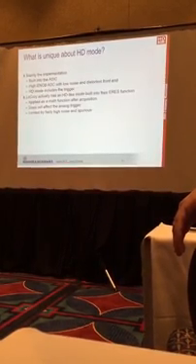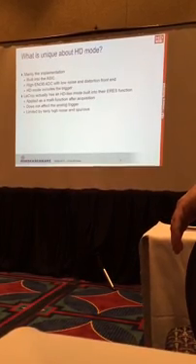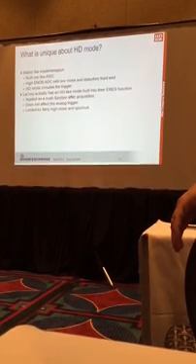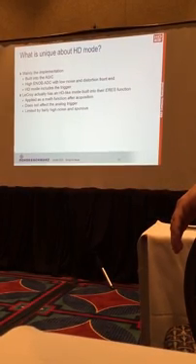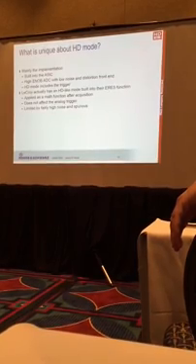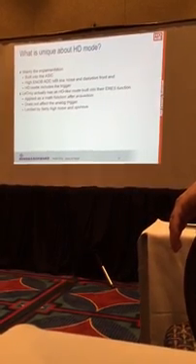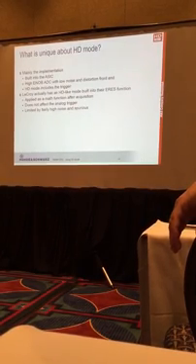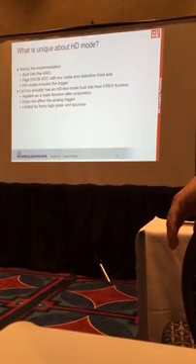And LeCroy has a pretty big spurious problem. And it turns out their spurs are a little bit funny in the sense that their spurs are way down at low frequencies because of the technology they use to calibrate the scope. It ends up shoving all the spurs down to low frequencies. So you tend to see what looks like phase noise almost running at low frequency. And so it's not as effective on their scope, especially at low frequencies. So those are the reasons that it's really unique for us. We do it in hardware, and our ADC happens to be more linear than anybody else's, so it tends to work better.